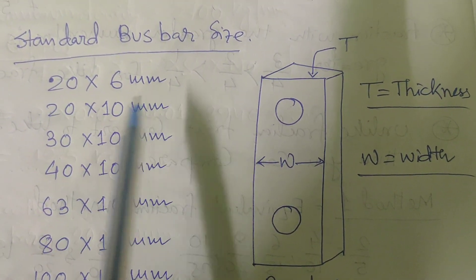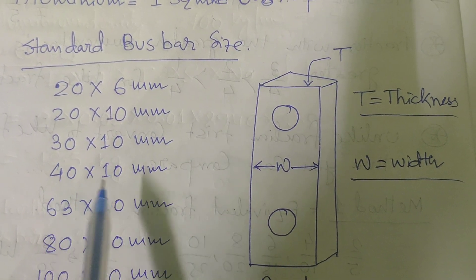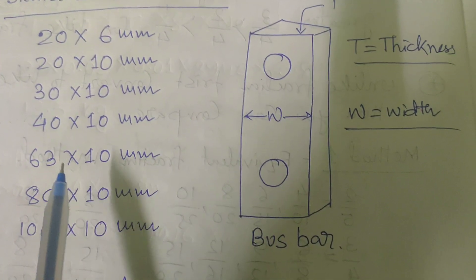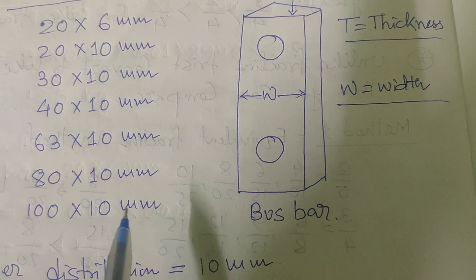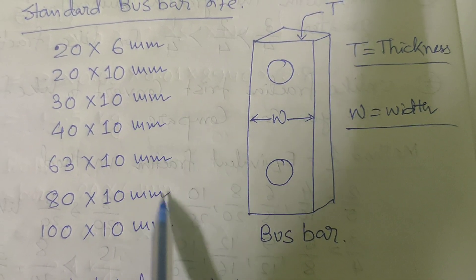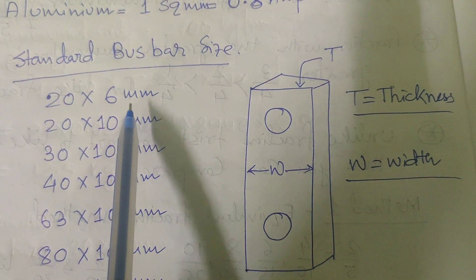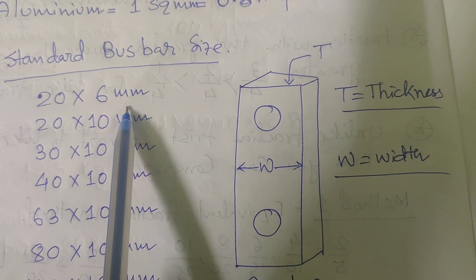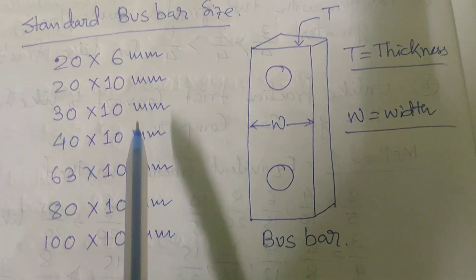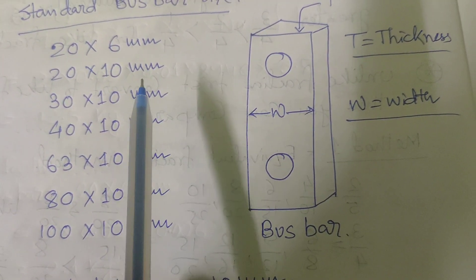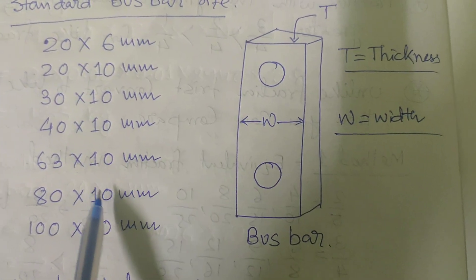Standard busbar sizes are: 20×6 mm, 20×10 mm, 30×10 mm, 40×10 mm, 63×10 mm, 80×10 mm, and 100×10 mm. The 6 mm thickness is used for neutral and earth flat connections, while 10 mm thickness is the standard for power distribution purposes.